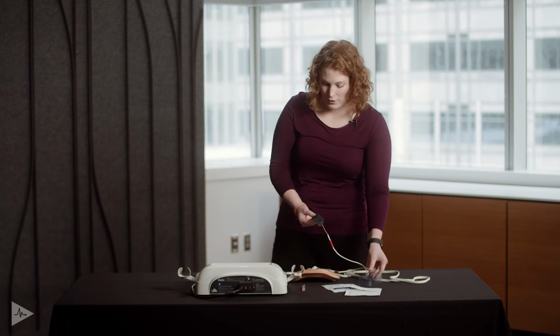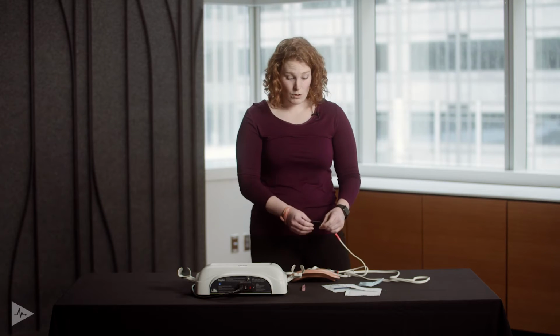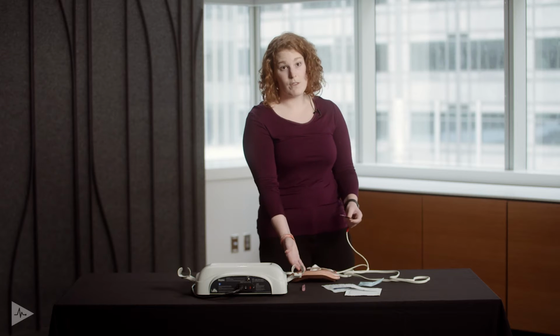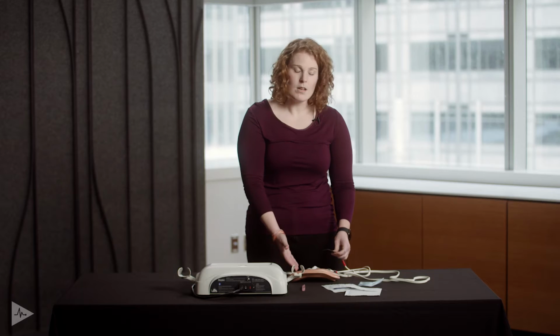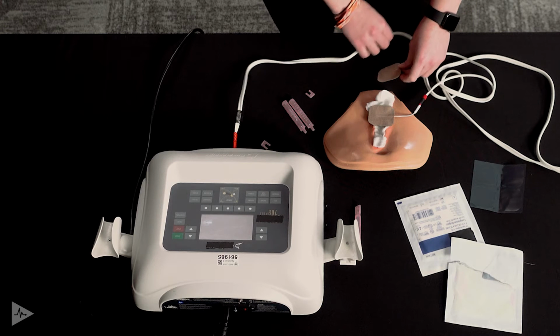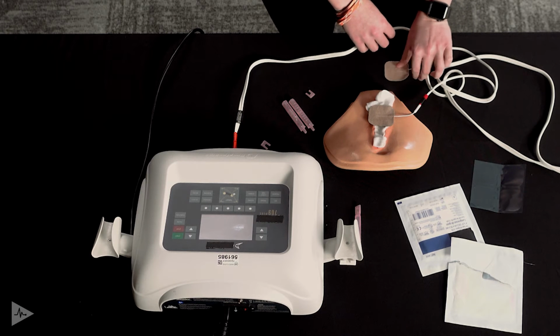If you had a real patient, you would want to ensure this gauze in the wound bed is not able to be moved during the treatment. You would next place your other electrode proximal to the wound bed. So if this was your abdomen, you'd want to place it above the actual wound of the abdomen. Since our model is not that big, we'll place it here to demonstrate.